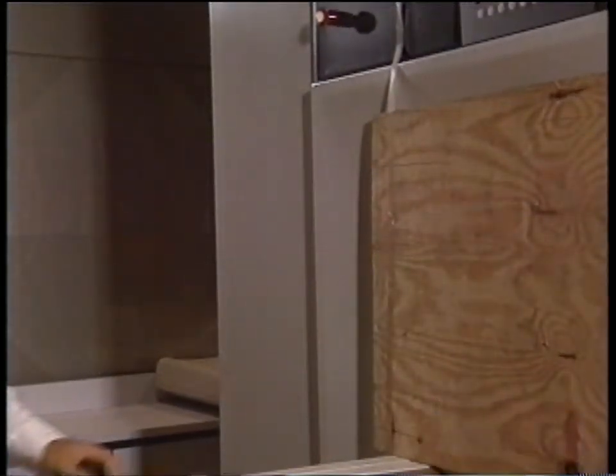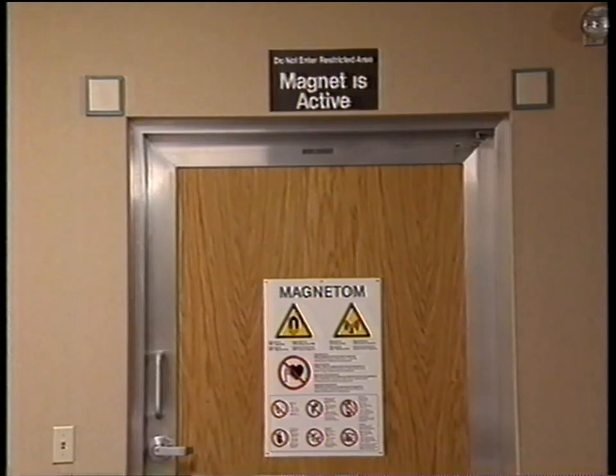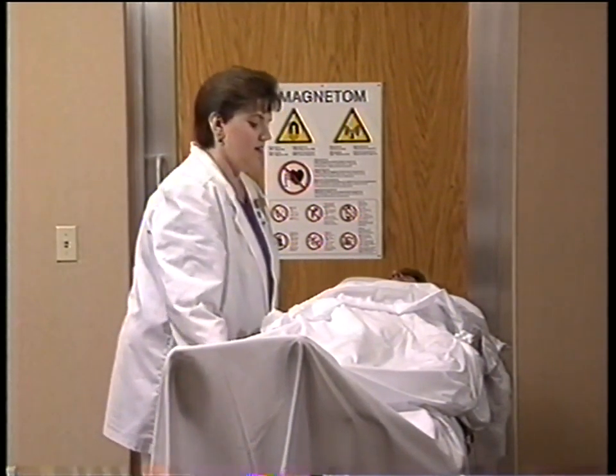So it's important that we check our clothing for ferromagnetic objects before we enter the magnet area. This is what would happen if anyone with any ferromagnetic equipment — a janitor walking in with a metallic mop or an anesthesiologist walking in with medical equipment — entered the room. It would take perhaps one step before something was extracted from them and pulled into the magnet. Whenever you take any equipment into the magnet room, you must be sure that it is compatible with MR — in other words, it must be non-magnetic.